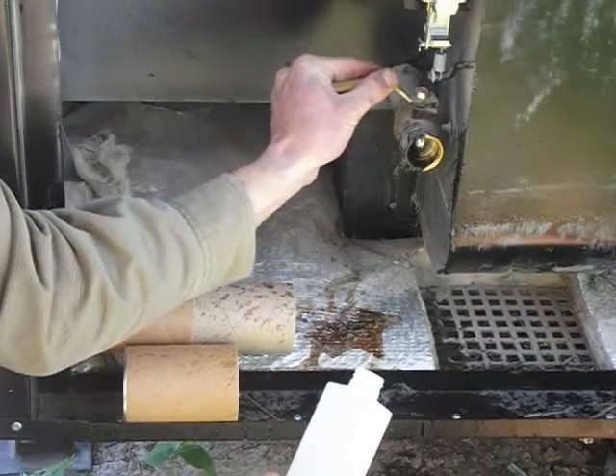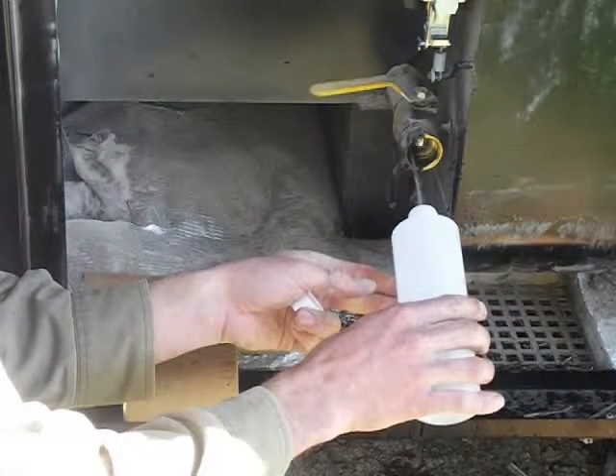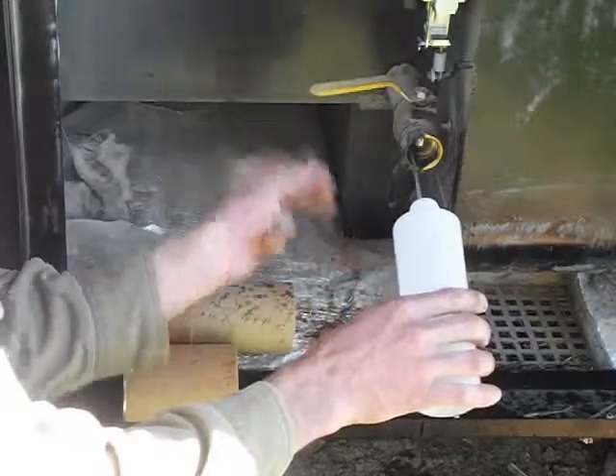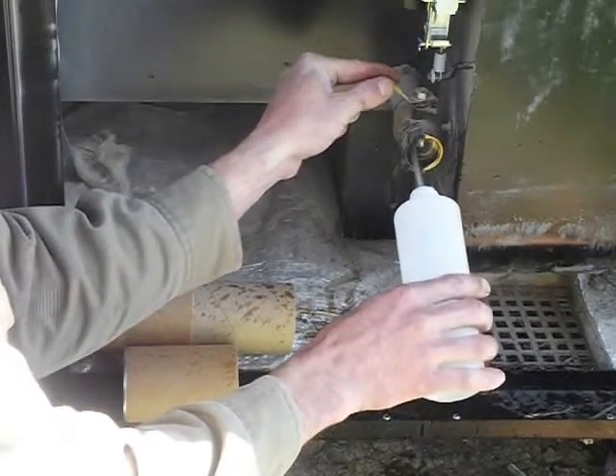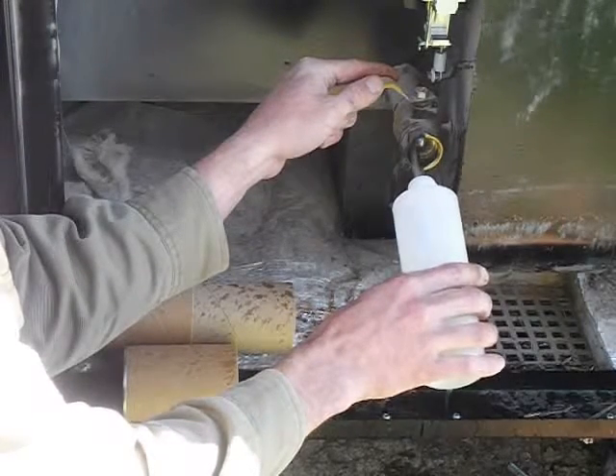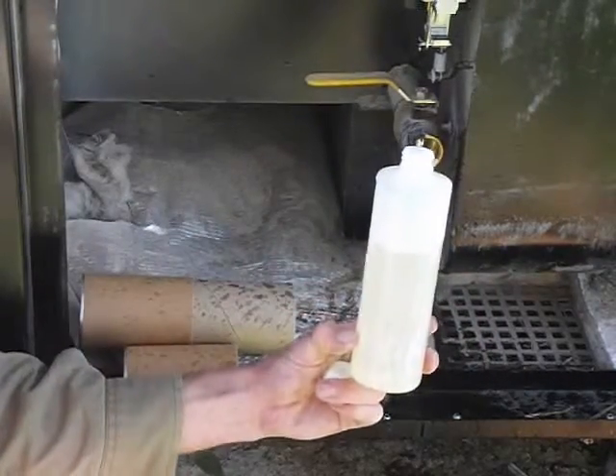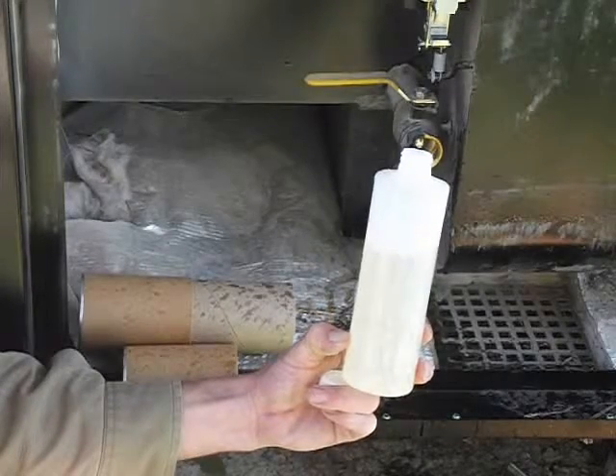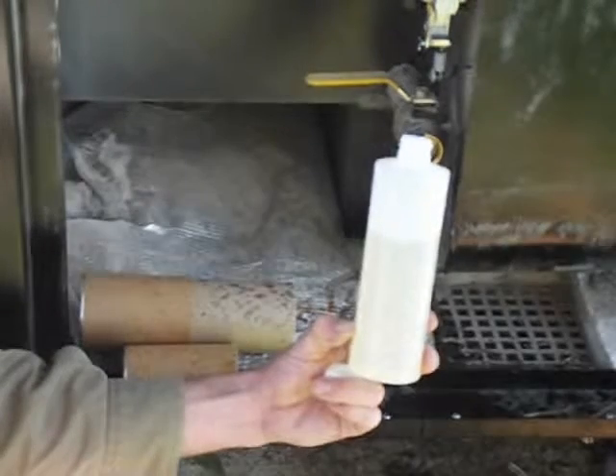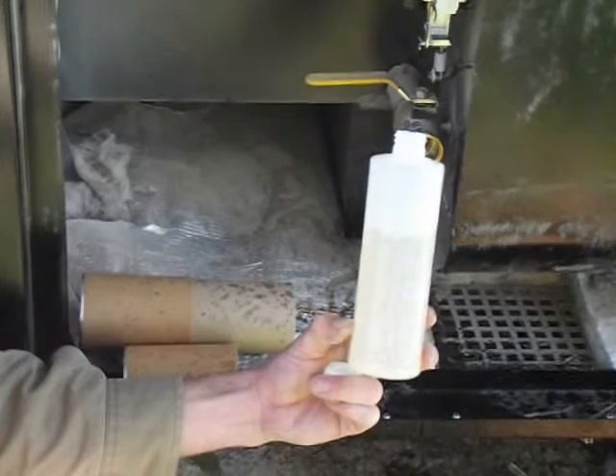Now that it's flushed out, I'll open it up to just a thin stream — or you could have a larger container and catch it in; it might be quicker. You can see it looks a little bit yellow, but that's normal as the water has been circulating in the system for a year or two. It's not the brown, sloppy looking water that you would see in an untreated furnace.